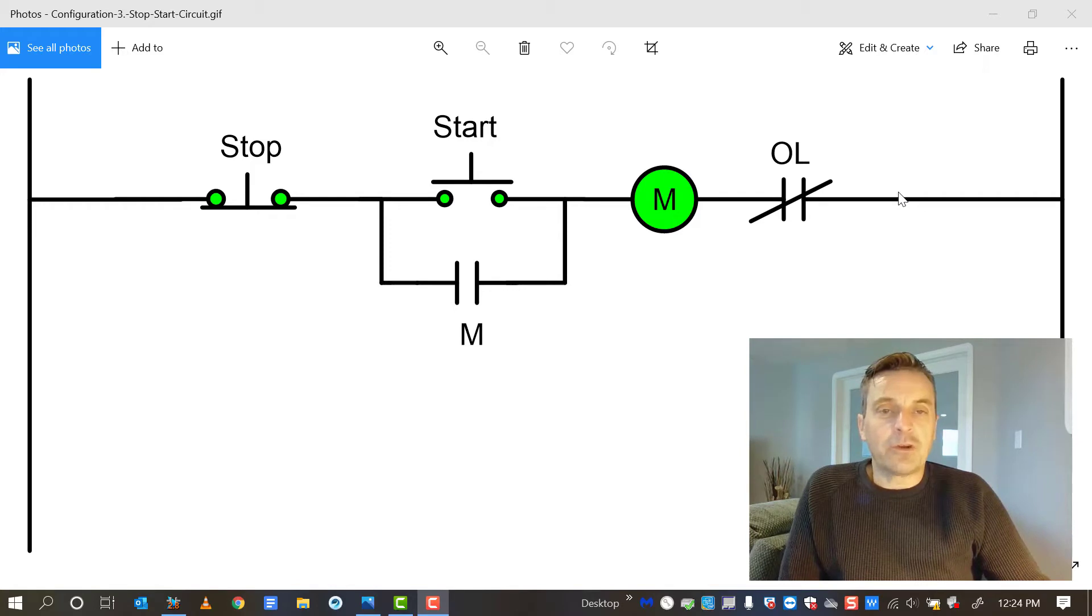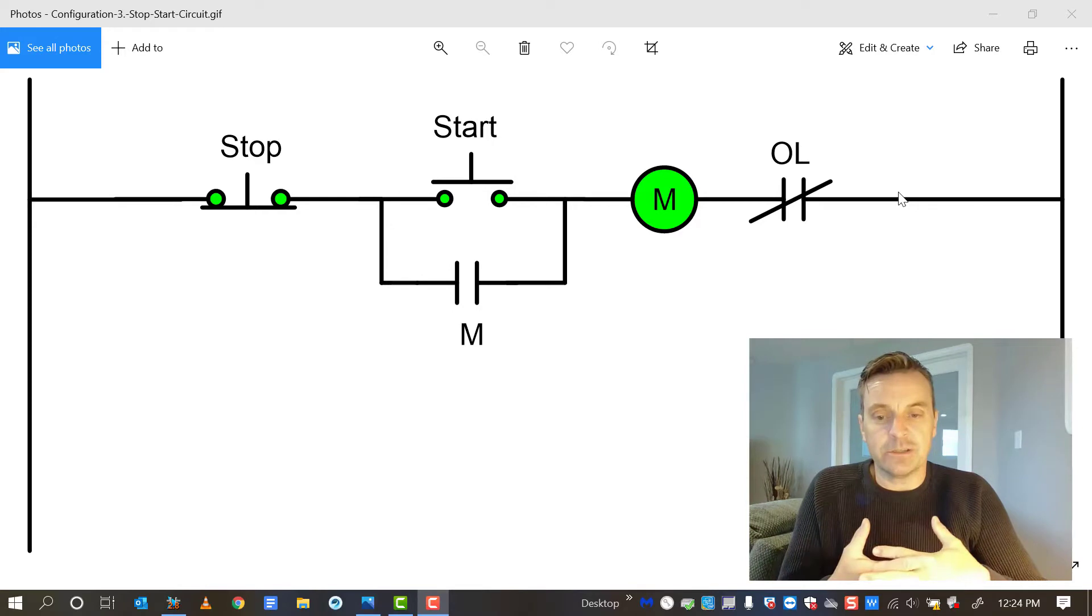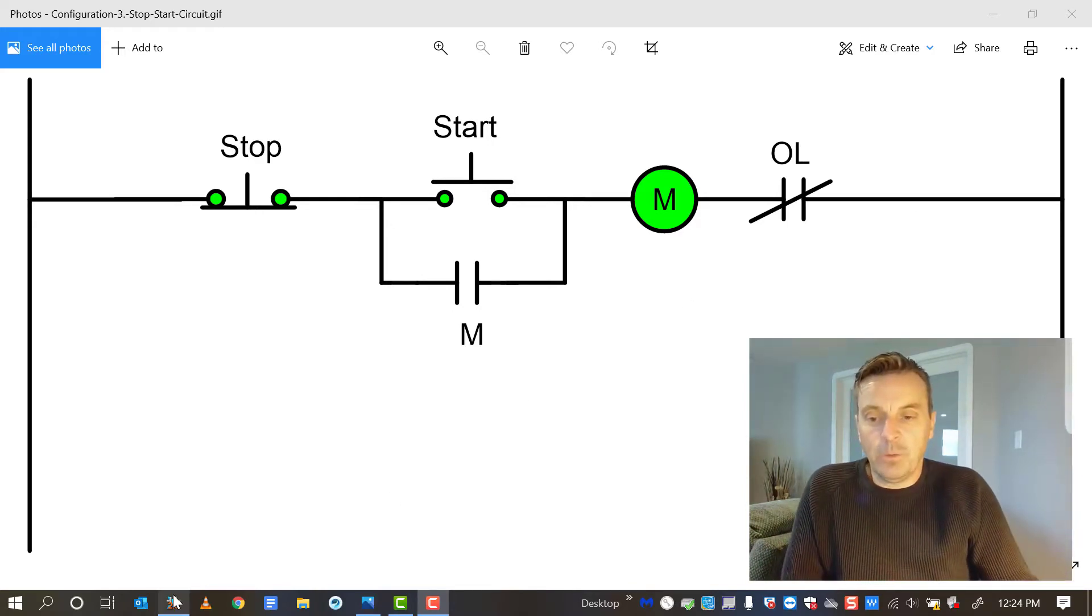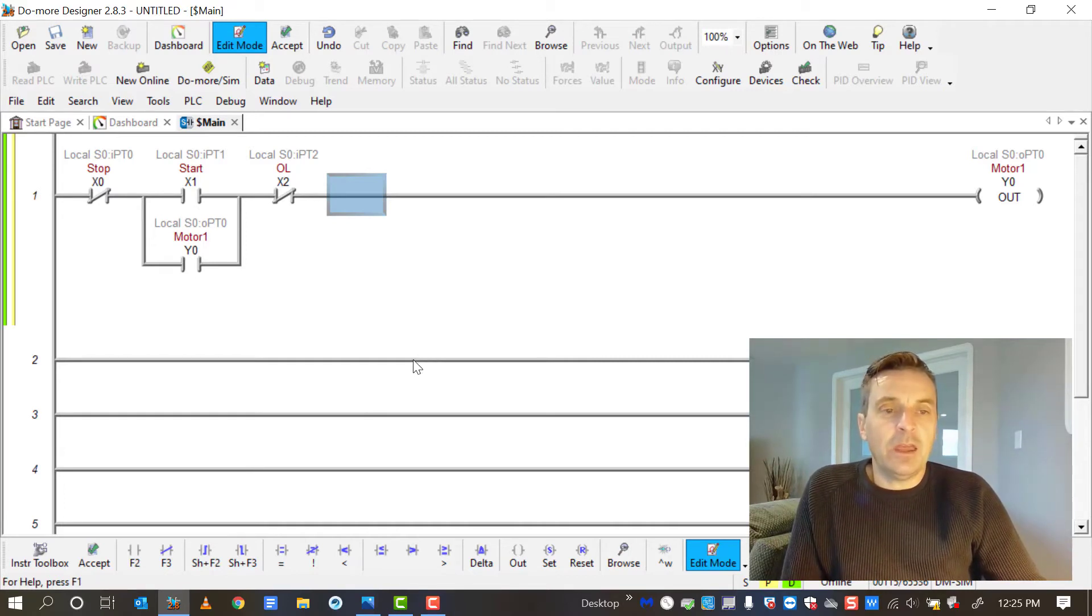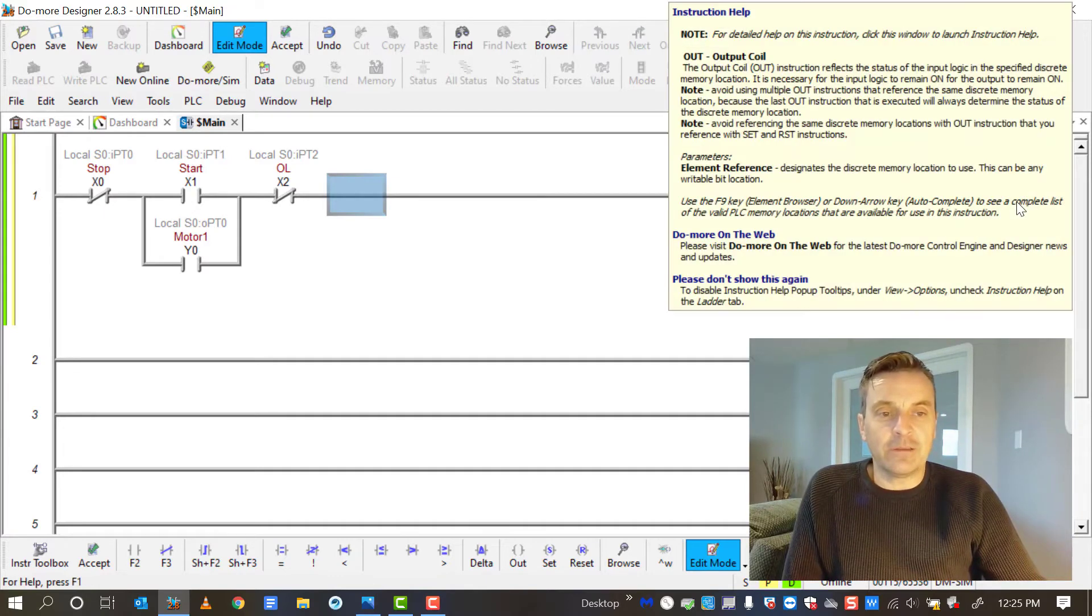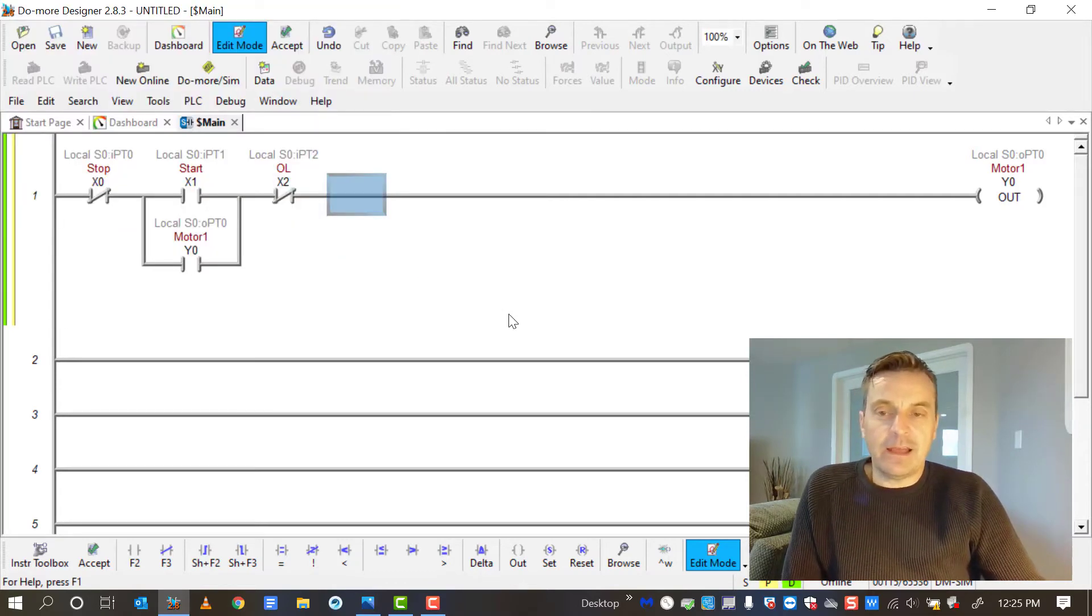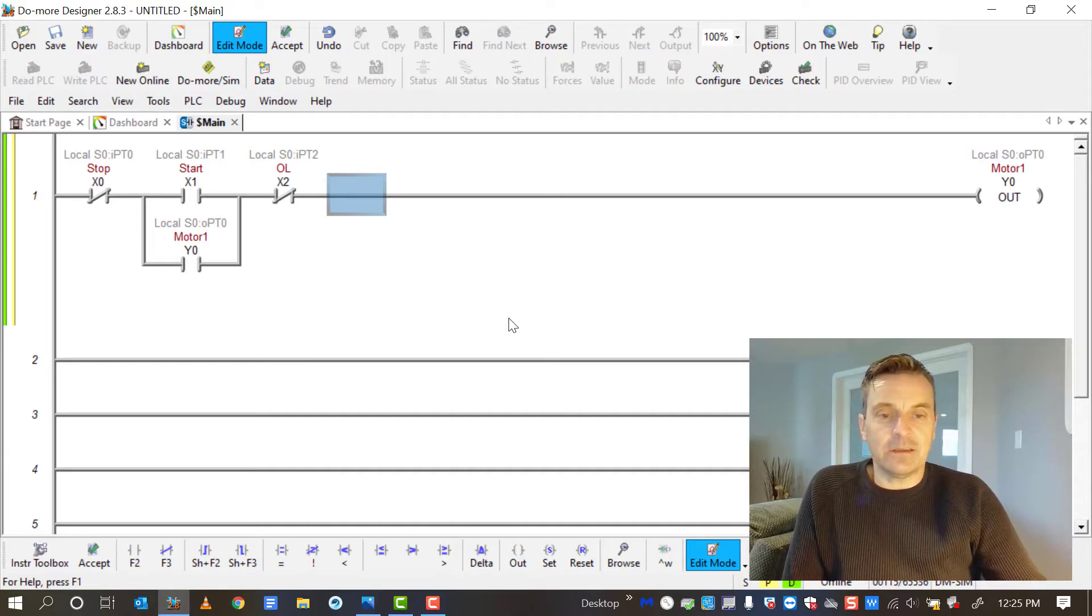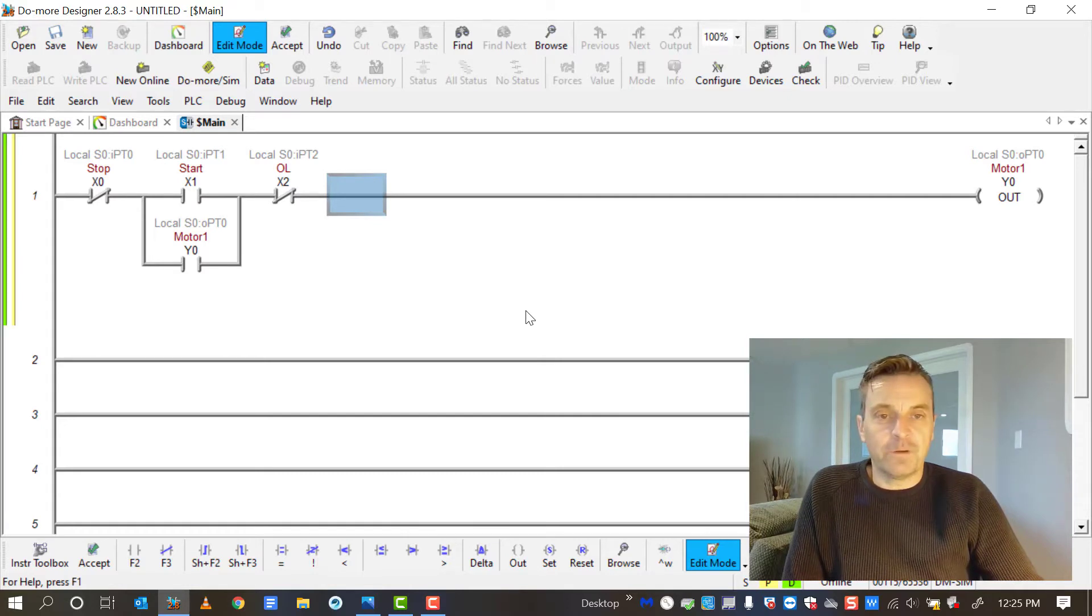So when we try to convert this diagram that we're so familiar with as electricians and convert that to a PLC program, we end up creating something that looks like this. Now again, it's not exactly the same, and you'll notice that the output for the motor coil is at the far end, the right side, and the overload is on the other side of it. That's fine, it won't really affect anything, it's just in ladder logic, the output has to be the last thing on the rung in order for it to function.